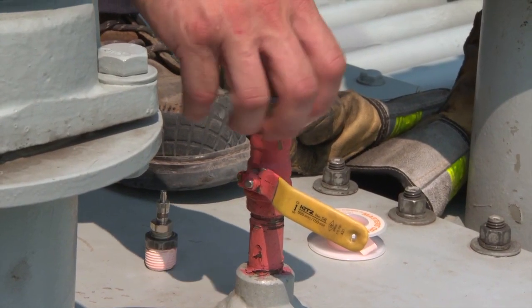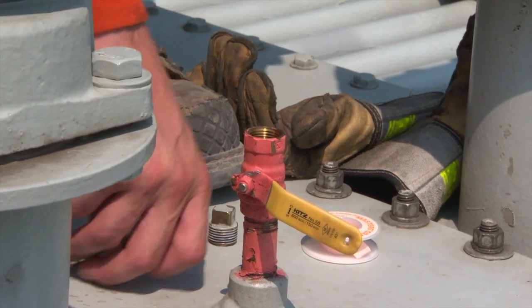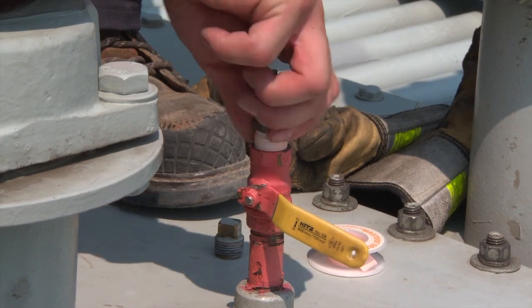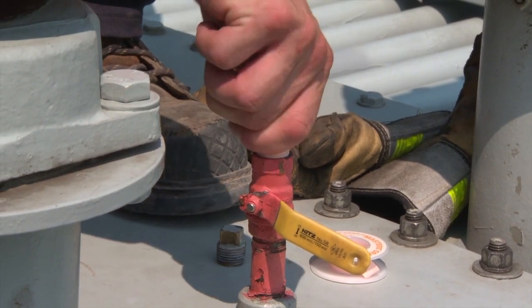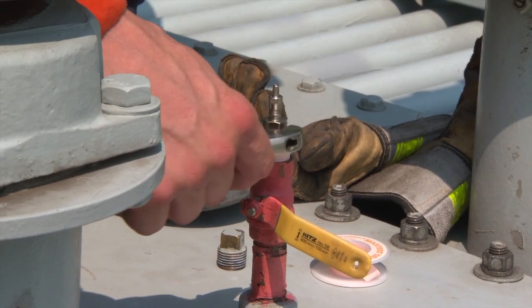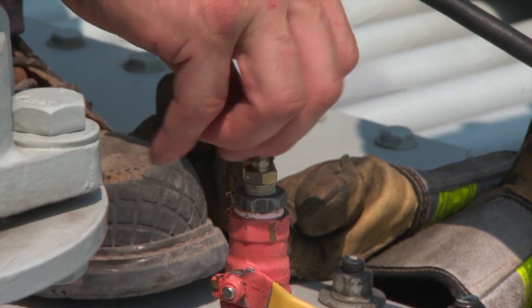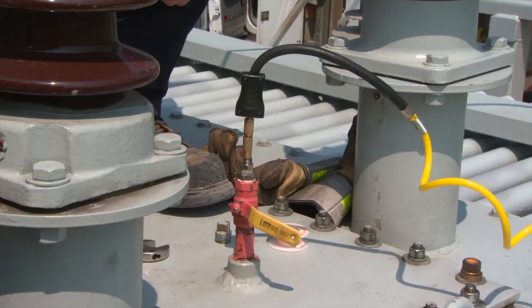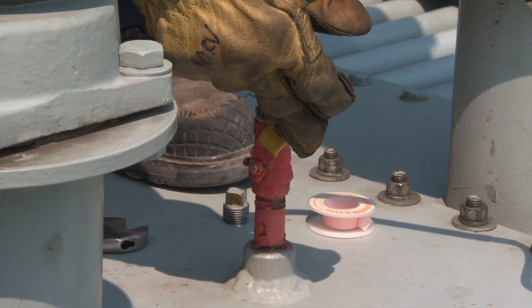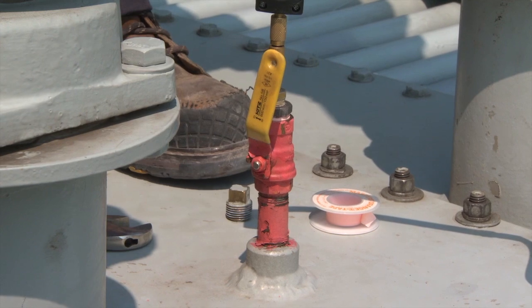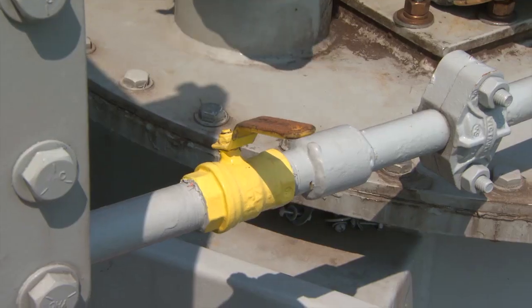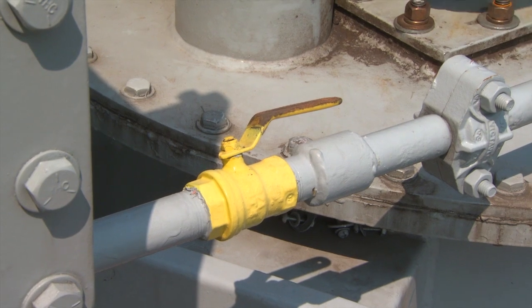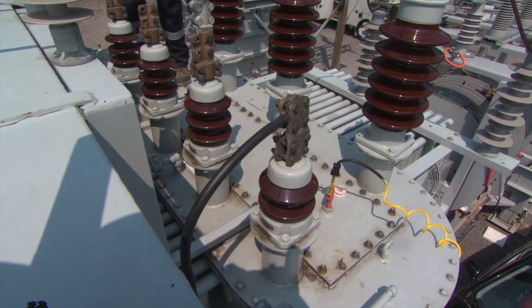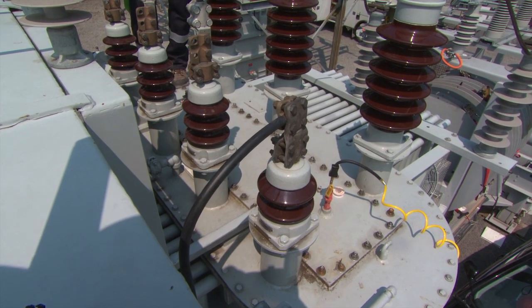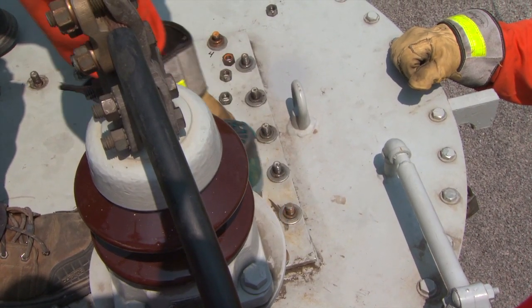When adjusting the links, the first step is to pump some of the oil from the main tank into the conservator in order to be able to remove the manhole cover without spilling oil. This can be done several ways. In this case, the RME is installing an air fitting on a valve at the top of the transformer bank and attaching an air compressor to the fitting. He is then pumping air into the top of the tank, forcing oil to go back into the conservator tank. Once the oil gets down past the piping, you will hear air gurgling up the pipe. This is when you should stop pumping air and shut the conservator tank pipe off. You can then remove the main tank manhole cover.